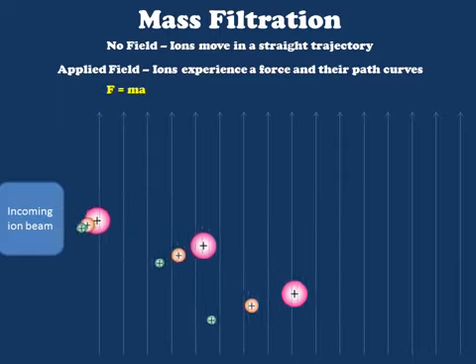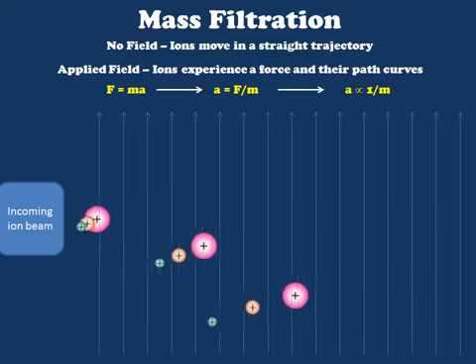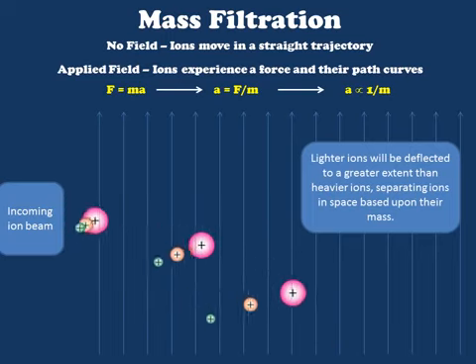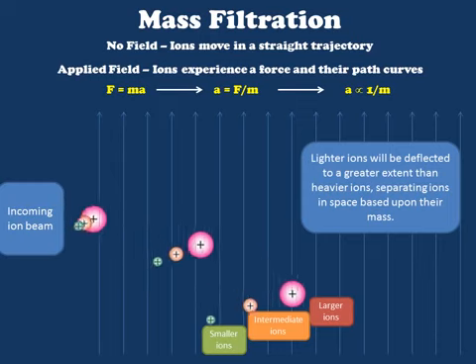Because force is equal to mass times the acceleration of an object, we can calculate that the acceleration of any object must be equal to the force divided by its mass. In this instance, because force is constant for all ions, we can determine that acceleration is proportional to the reciprocal of the ion's mass. In other words, lighter ions will be deflected to a greater extent than heavier ions, causing them to be separated in space. The smaller green-colored ions are moving with a greater degree of curvature, meaning they reach the bottom of the screen at a location closer to the source. Now that we have separated our ions in space, we need to detect exactly where they have gone so that we can back-calculate their masses.